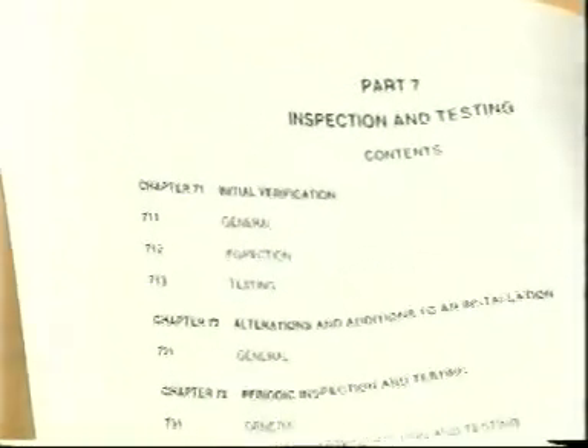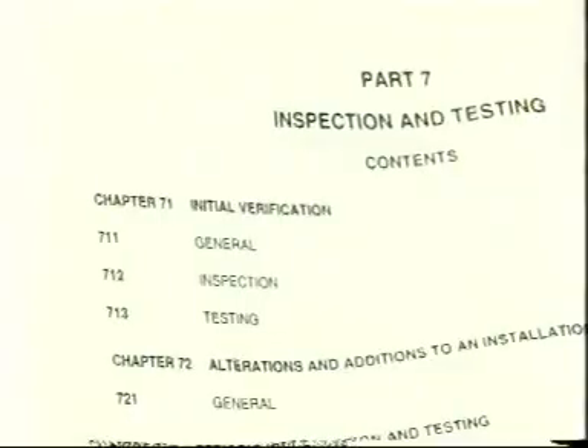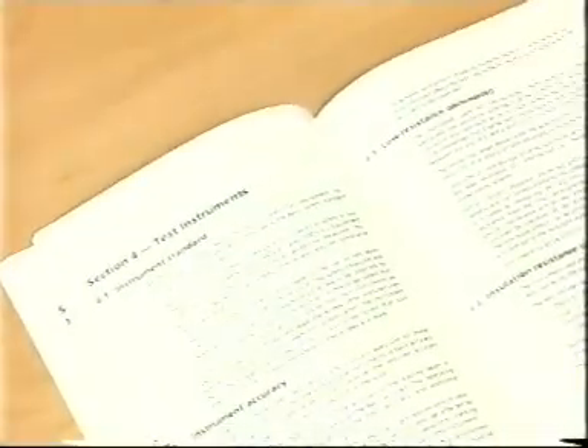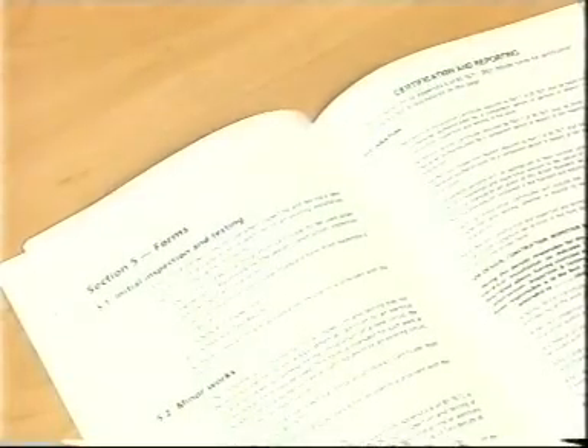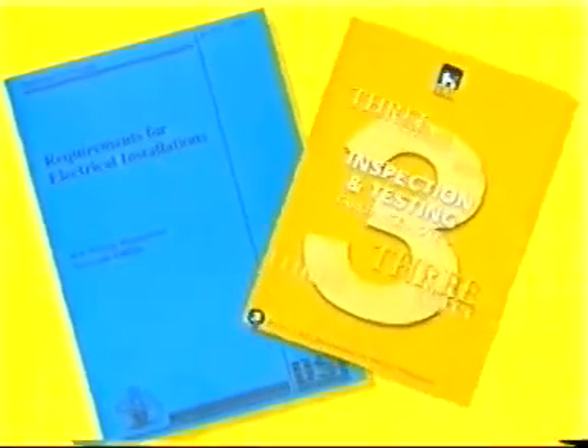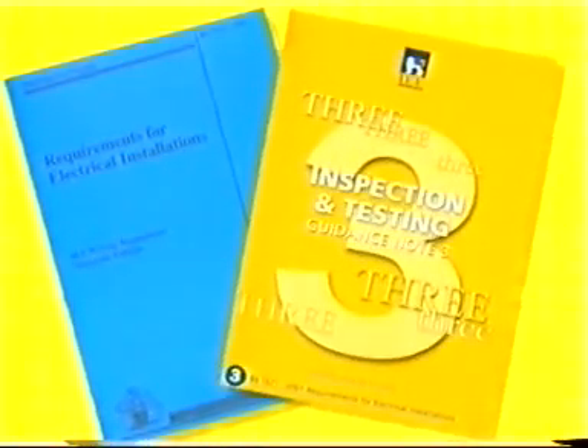It's essential the verifier is familiar with requirements of Part 7 of the wiring regulations and relevant parts of Guidance Note 3. Section 2 of Guidance Note 3 is for initial verification, new works, and Section 3 for periodic verification of existing installations. Sections 4 and 5, together with the appendices, are necessary for reference in conjunction with Sections 2 and 3. The content of this video is not intended to replace BS 7671 or IEE guidance material, which should be consulted in all cases of doubt.